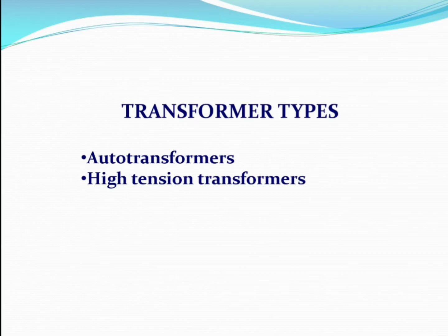Now here in X-ray circuit, we will be learning basically two types of transformers, that is autotransformer and high tension transformer. The autotransformer can function both as a step-up transformer as well as a step-down transformer, whereas the high tension transformer is a step-up transformer.